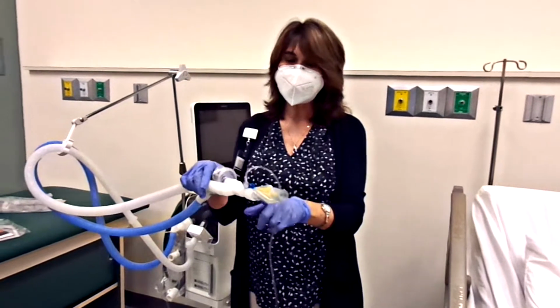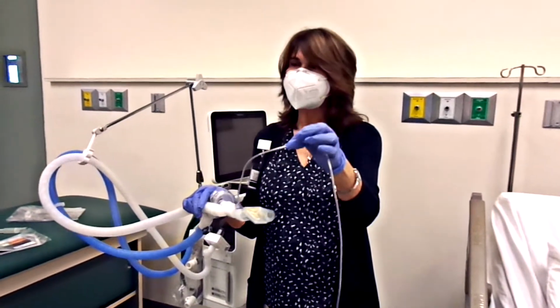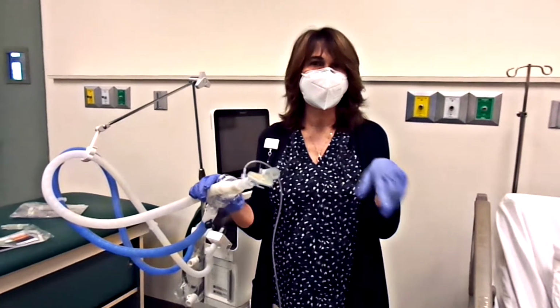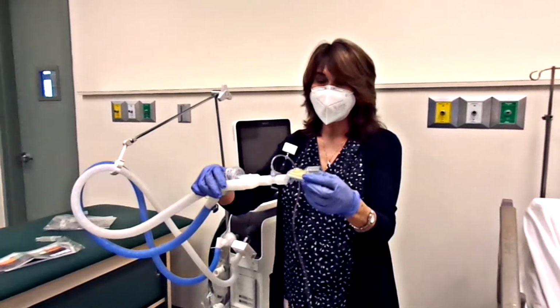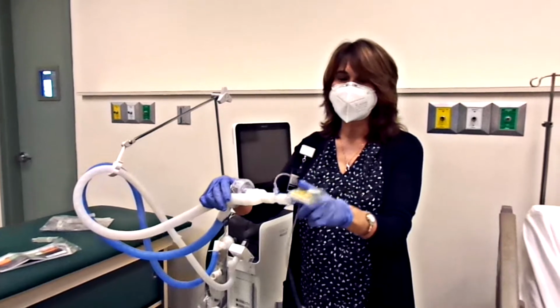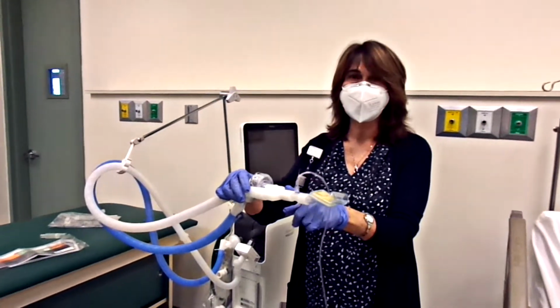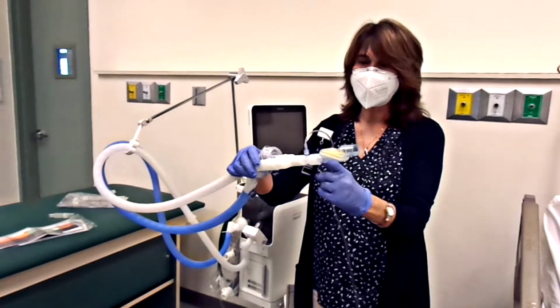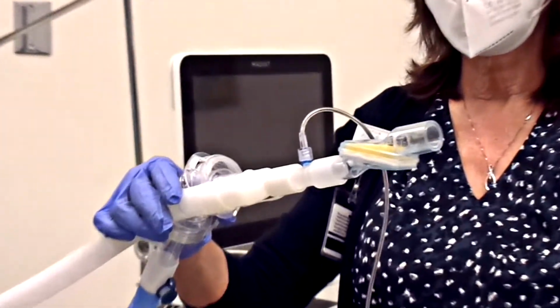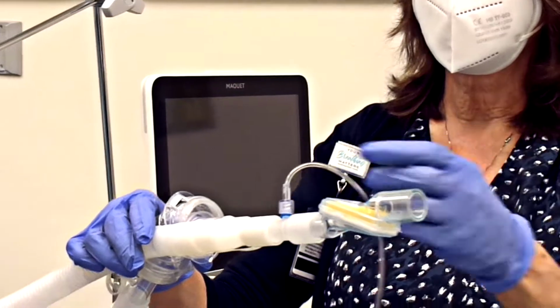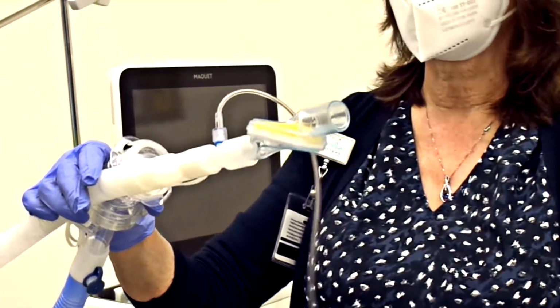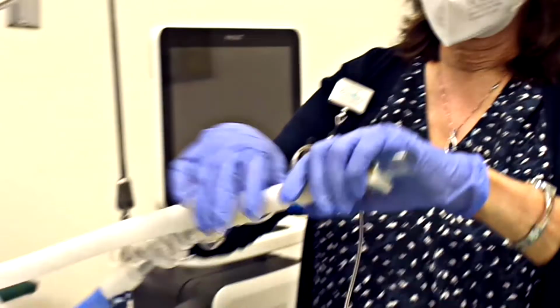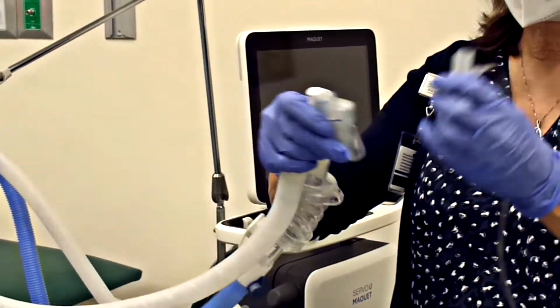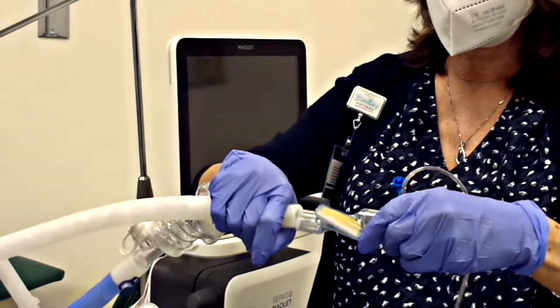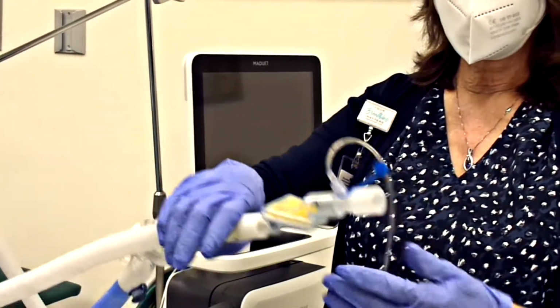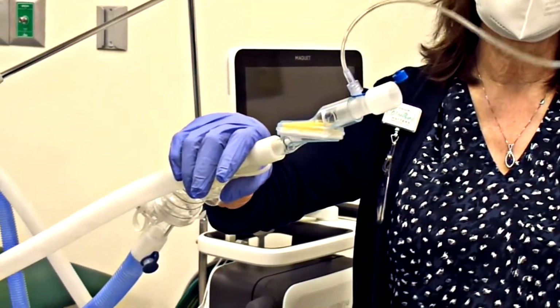All right, so when you're putting the adapter in line, anytime moisture gets in here, it messes up your waveform. So what I recommend is you put the adapter between the HME and the Y. So you'll get your inspired air, bringing everything down to 0, and then your exhaled air will come through, and then you'll see the CO2 climb during exhalation. If you put it closer to the patient, it gets wet, you have to change it quite often. So this would be okay, but you end up having to change this tubing a lot.